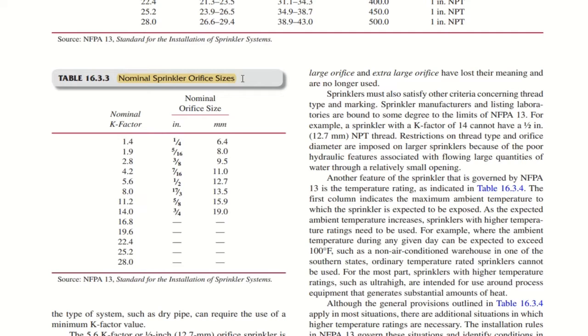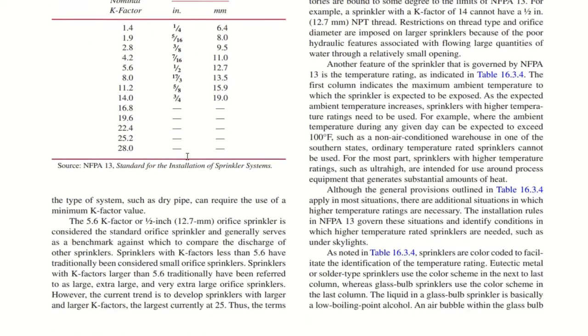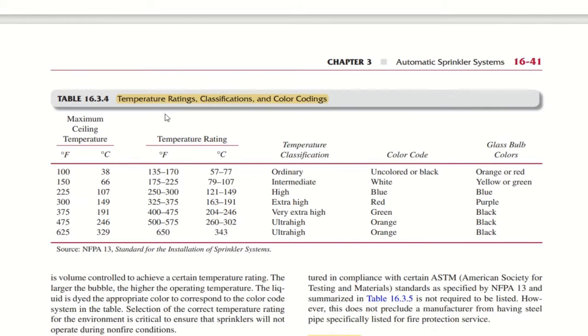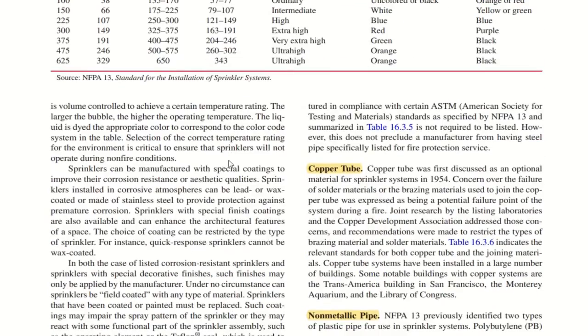Nominal sprinkler orifice sizes: if you are considering a nominal K factor of 5.6, the nominal orifice size will be half inch, so in mm it will be 12.7 mm. If you are going with an 11.2 K factor sprinkler, then the orifice size will be 5/8 inch or 15.9 mm. This is an important table which you need to go through. Here they also cover temperature rating classification and color coding, since it relates to the various sprinklers. So this table is also included here in chapter 3.